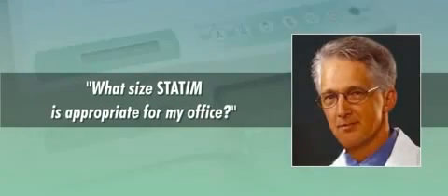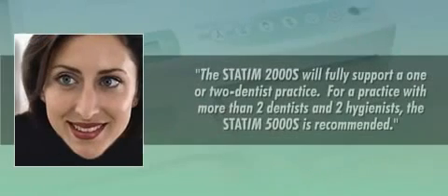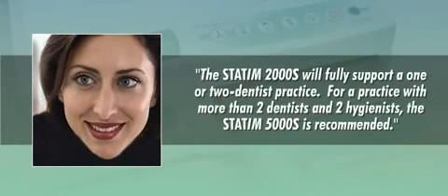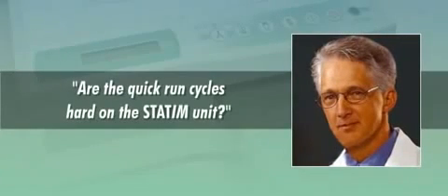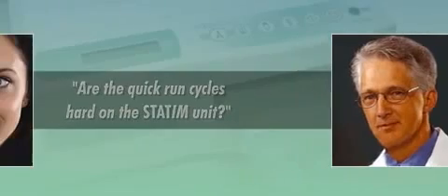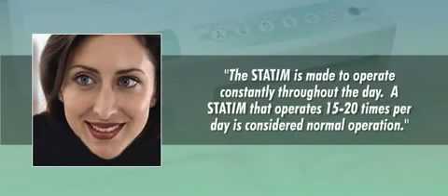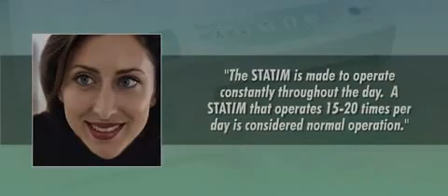What size STATIM is appropriate for my office? The STATIM 2000S will fully support a 1 or 2 dentist practice. For a practice with more than 2 dentists and 2 hygienists, or where larger implant instruments are used, the STATIM 5000S is recommended. Are the quick run cycles hard on the STATIM unit? The STATIM is made to operate constantly throughout the day. A STATIM that operates 15 to 20 times per day is considered normal operation.